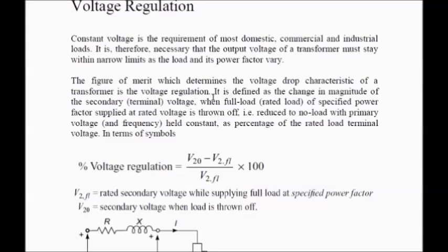A proper definition of voltage regulation can be like this. It is defined as the change in magnitude of the secondary voltage when full load of specified power factor supplied at rated voltage is thrown off, that is reduced to no load, with primary voltage held constant, as a percentage of rated load terminal voltage.